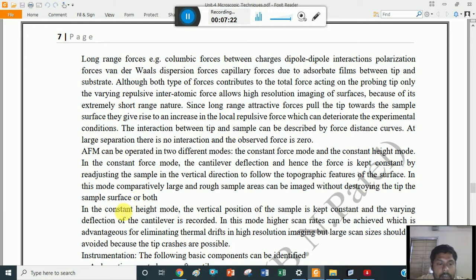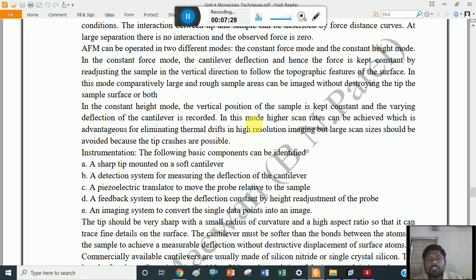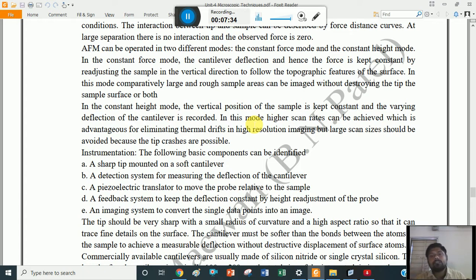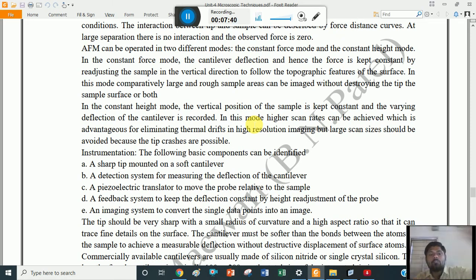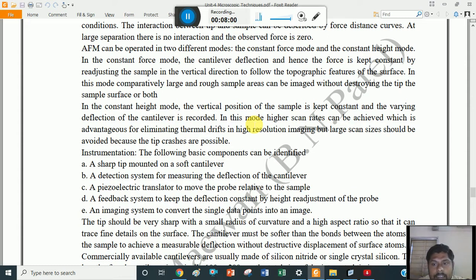The sample surface is also not destroyed. In constant height mode, the vertical position of the sample is kept constant — the surface is fixed and the cantilever tip moves. The varying deflection of the cantilever is recorded. In this mode, higher scan rates can be achieved, which is advantageous for eliminating thermal drift in high resolution imaging, but large scan sizes should be avoided because tip crashes are possible.